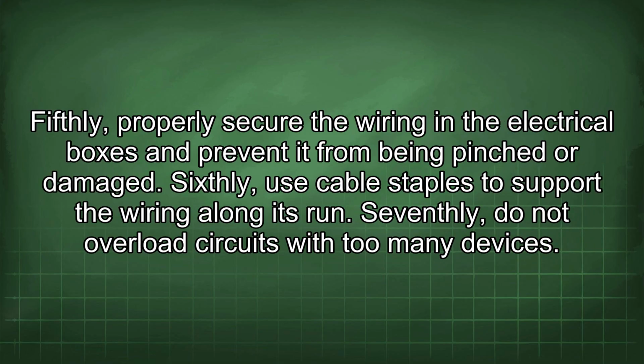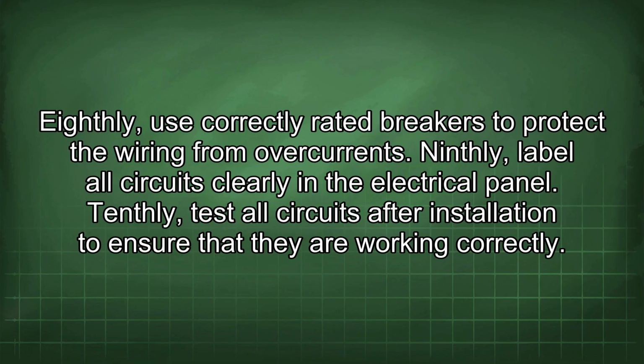Fifthly, properly secure the wiring in the electrical boxes and prevent it from being pinched or damaged. Sixthly, use cable staples to support the wiring along its run. Seventhly, do not overload circuits with too many devices. Eighthly, use correctly rated breakers to protect the wiring from overcurrents. Ninthly, label all circuits clearly in the electrical panel. Tenthly, test all circuits after installation to ensure that they are working correctly.